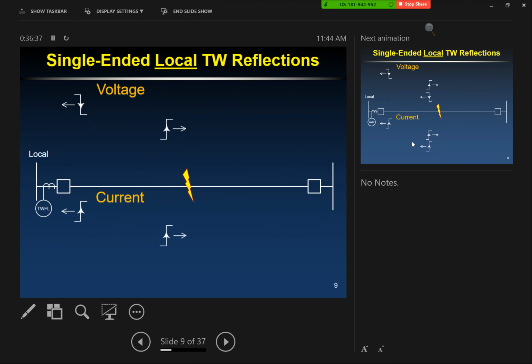It travels back to the fault. Again, another short condition, right? This is a perfect short, or maybe has some resistance, but it's less than the impedance of the line, so we get another reflection back. No polarity change on the current, and it flows back.